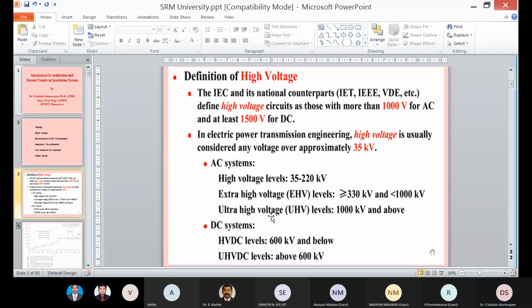And similarly, when it comes to DC systems, 600 kV and below is called HVDC, and above 600 kV usually comes under UHVDC. Right now we have HVDC in operation, and UHVDC is being commissioned in the northeastern part of India. I will cover that in the very next slide. May I move to the next slide, sir? You can please carry on, no problem. Fine, sir.